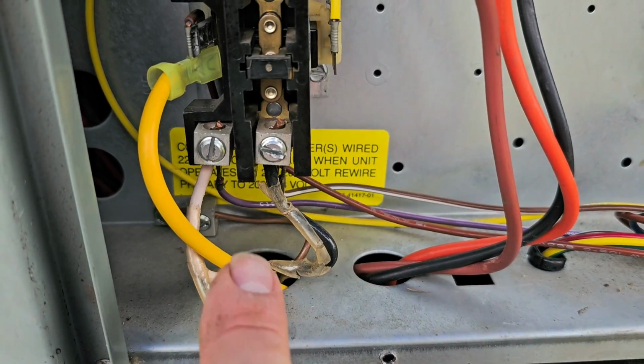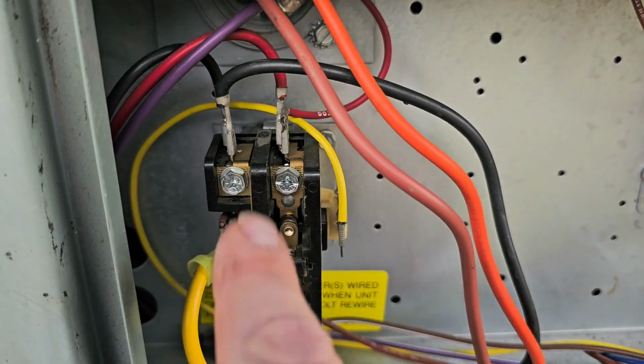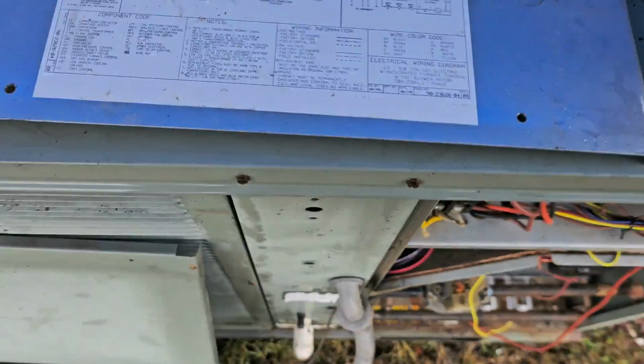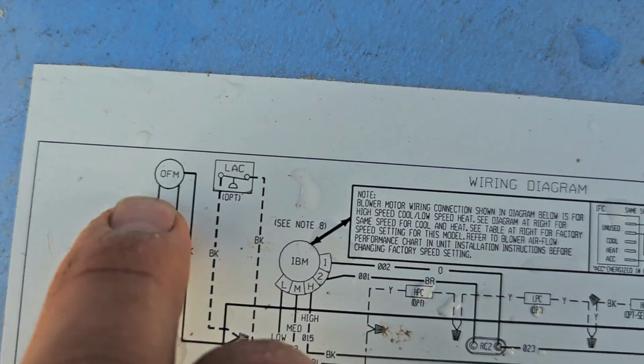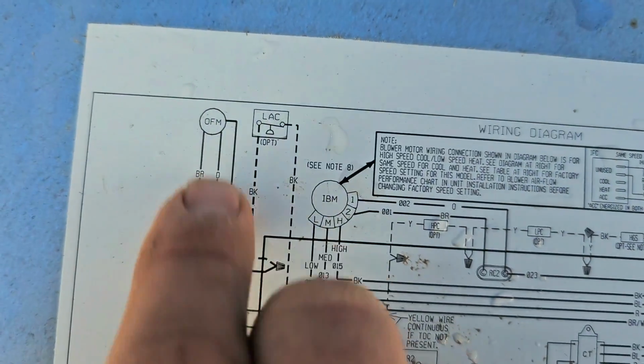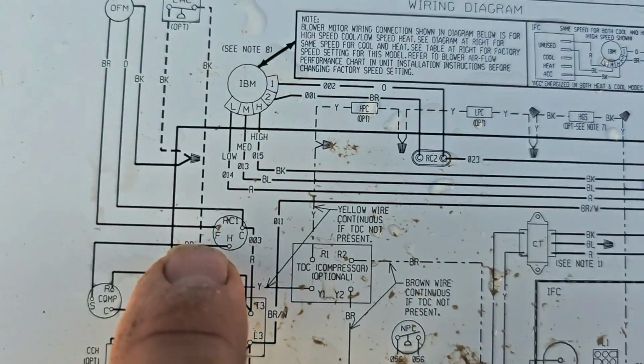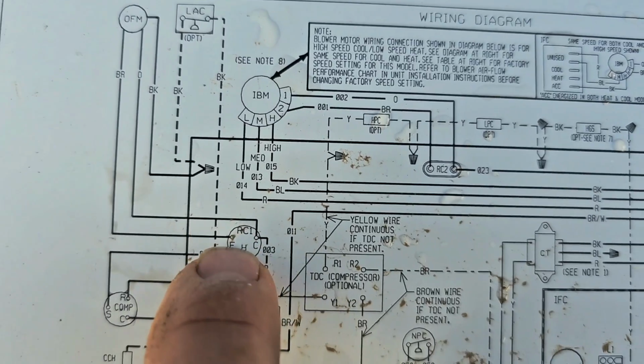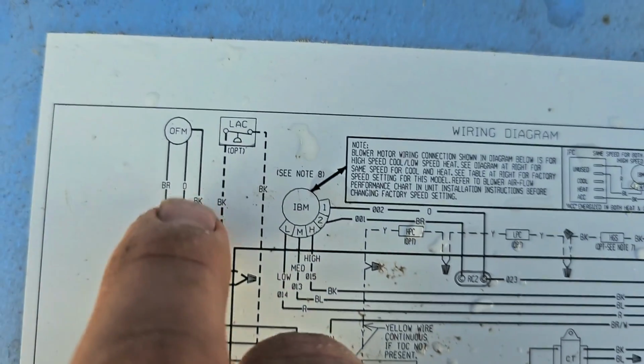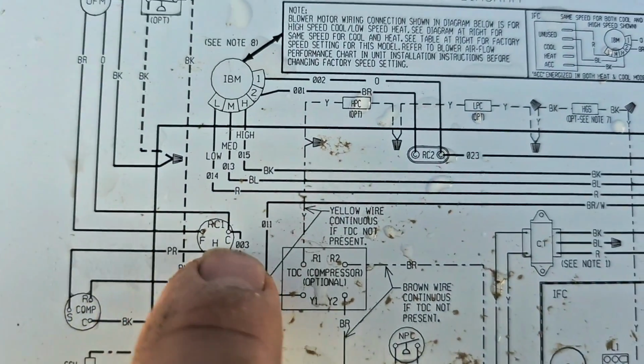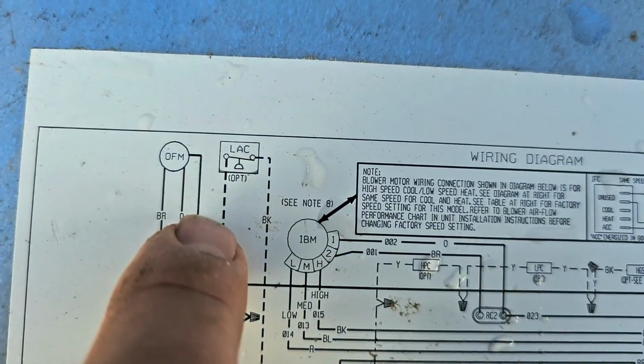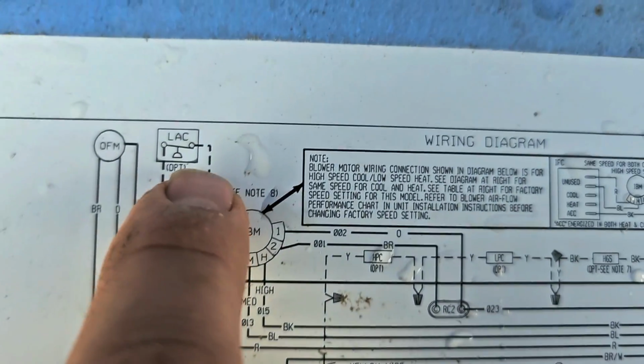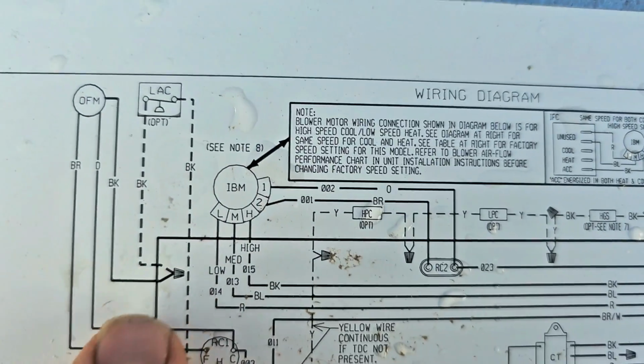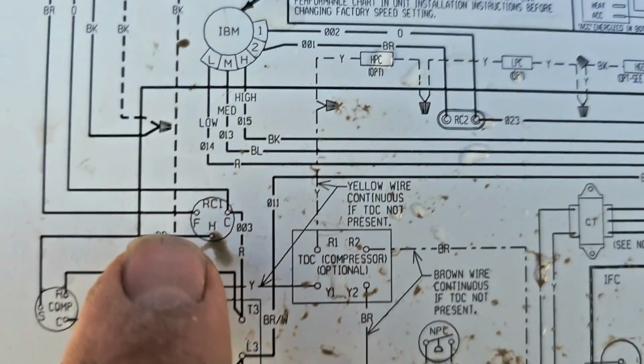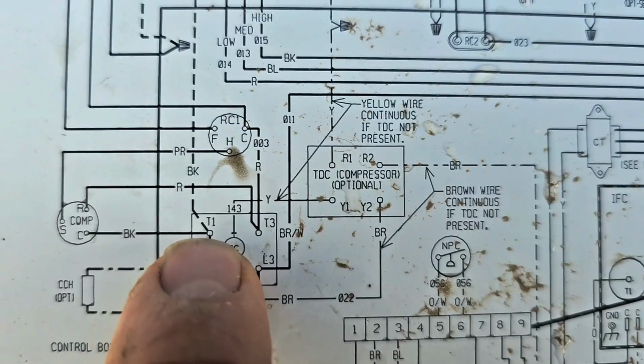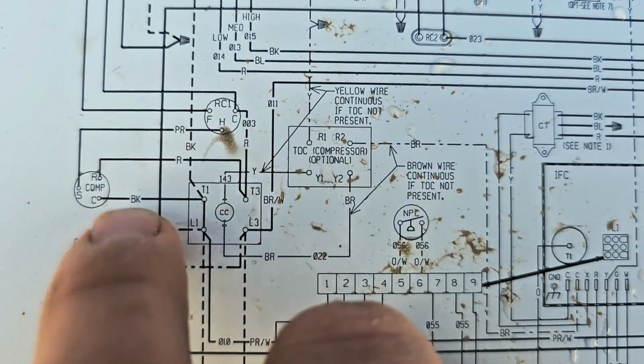So you've got line, which is the power coming into the contactor, load, which is the power going out. And if you want to read the schematic, you see it says OFM. That is outdoor fan motor. Brown wire, F. That's the dual capacitor right there. So F terminal. Orange, common, C of the dual capacitor. And then black, and this right here is LAC, which is optional, so we don't have that. So it goes straight to that side of the contactor, which connects to the other black wire that leads to the compressor.